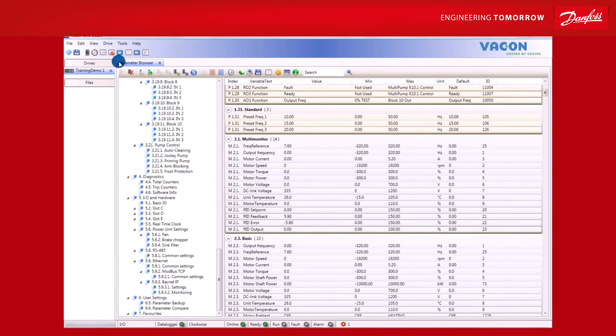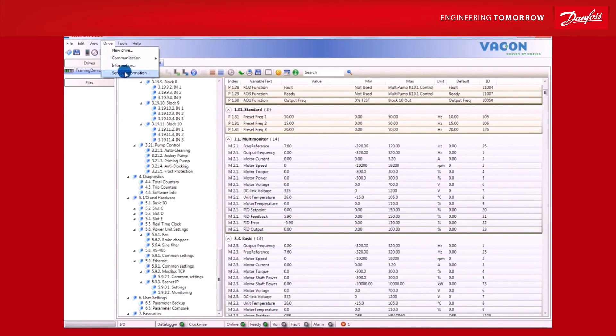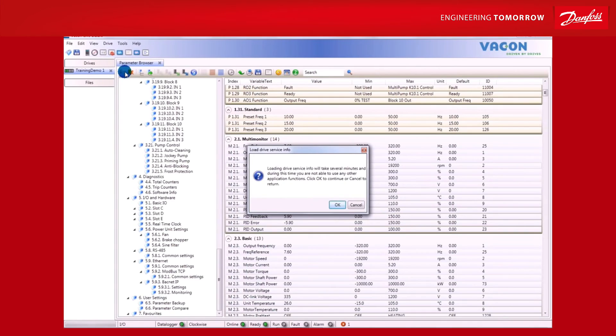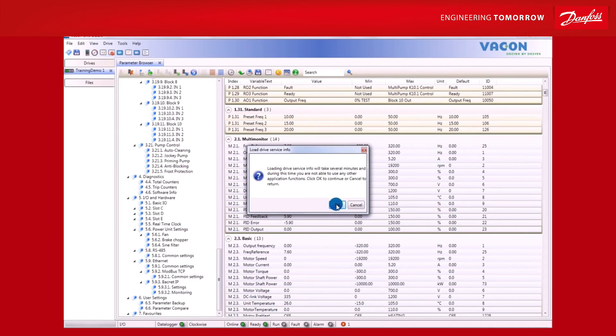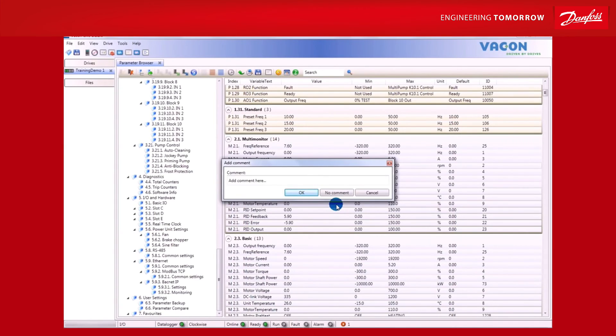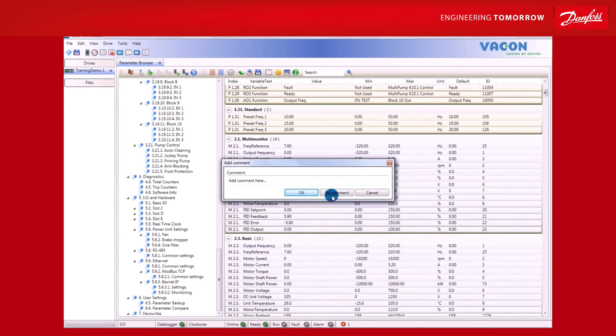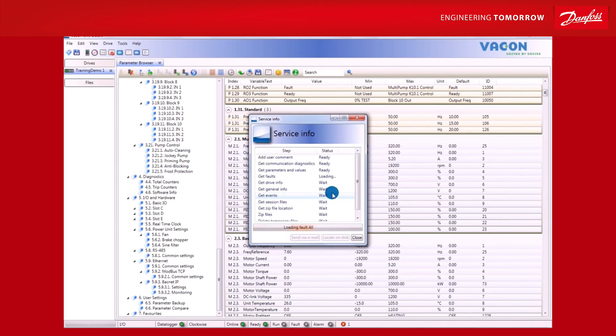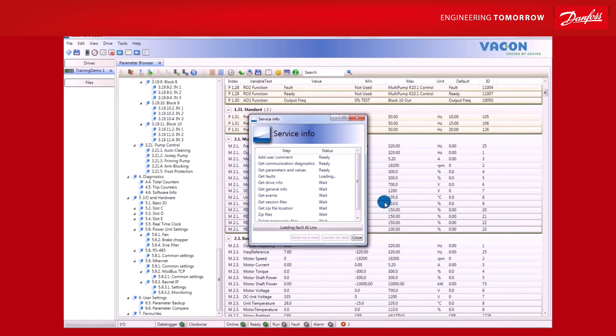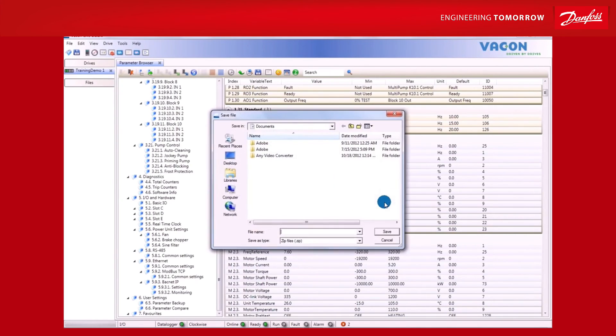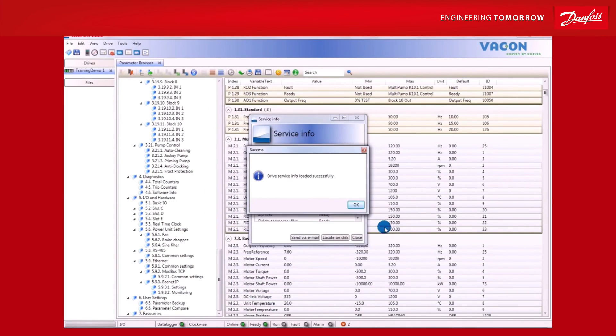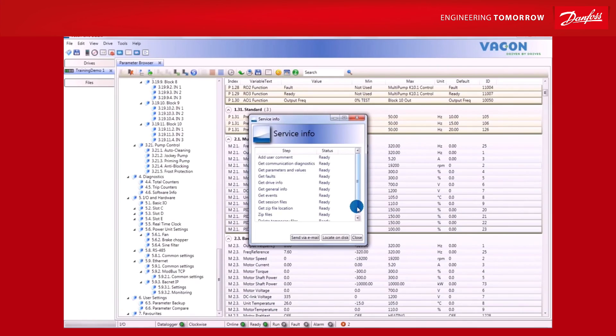Another handy tool you get with VaconLive is the Service Info feature. To access Service Info, go to Drive in the toolbar and select Service Information from the drop-down list. A window will then open. Click OK to start loading a Service Information report. You can add user comments and press OK, or alternatively, simply click No Comment. Once all the data has been gathered, a pop-up dialog will appear where you can name the Service Information file and either locate on disk or send via email according to your needs.